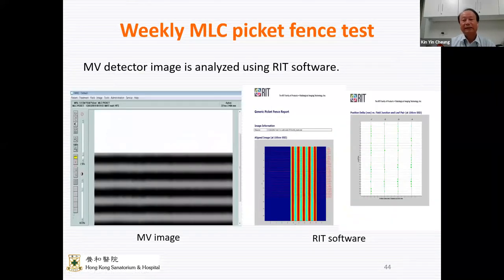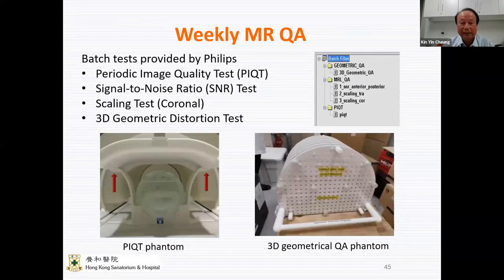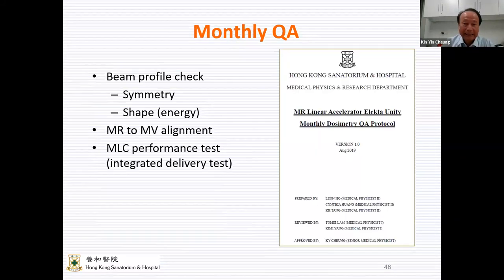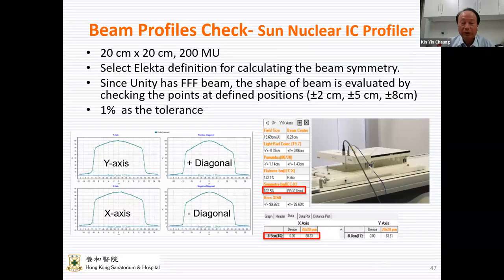And we also do a weekly picket fence check on the MLC. We also do a quality check on the MR image and also on the geometry accuracy of the MR image. And for monthly tests, we use a profiler to check the lateral X axis and Y axis profile, and also the two diagonal axis, and compare with the benchmark. After we did the water tank, we took a lot of benchmark data, including the profile, using a profiler.